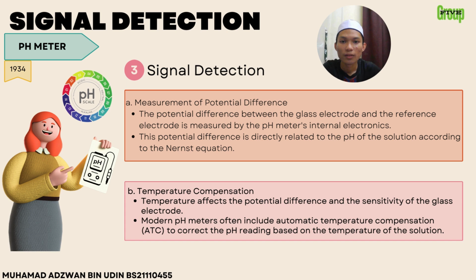Number three, signal detection: measurement of potential difference. The potential difference between the glass electrode and the reference electrode is measured by the pH meter's internal electronics. The potential difference is directly related to the pH of the solution according to the Nernst equation. For temperature compensation, the temperature affects the potential difference and the sensitivity of the glass electrode. Modern pH meters often include automatic temperature compensation (ATC) to correct the pH reading based on the temperature of the solution.